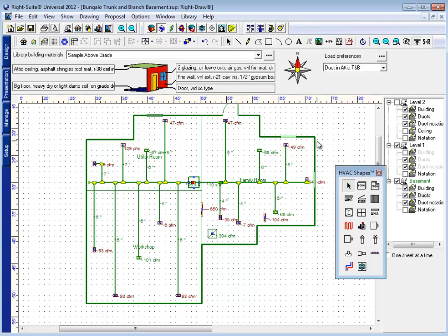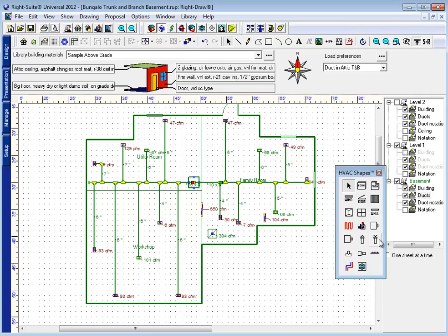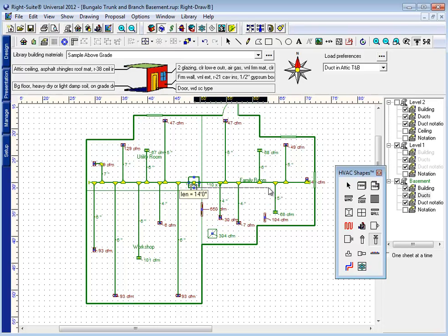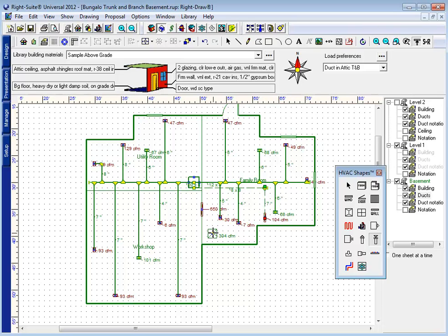The only other trick to doing this design is the fact that some of these, two of these registers in fact, are going to be high wall grills. So what I'm going to want to do when I'm connecting these registers is connect them the way I normally would as if they were simple floor grills. I could draw a trunk, if this is going to be a trunk and branch return, and run branches back to that trunk, like so.